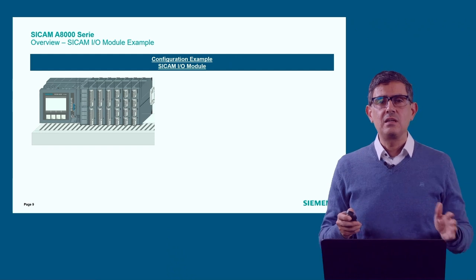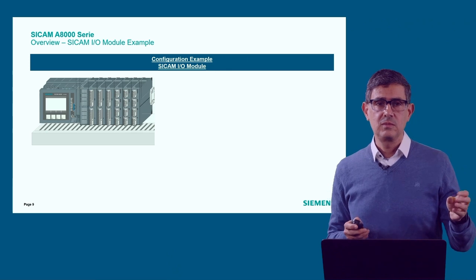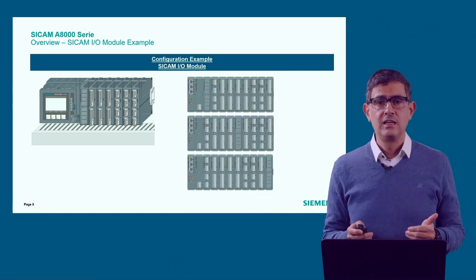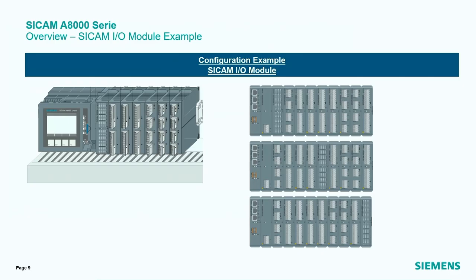These modules can be installed anywhere in the RTU as long as they are to the right of the power supply. In the CP8000, which has the built-in power supply, they can be connected directly to the right or further to the left. In the other RTUs they can be connected directly attached to the power supply, or in the middle of the input and output modules, or completely to the right — no problem.